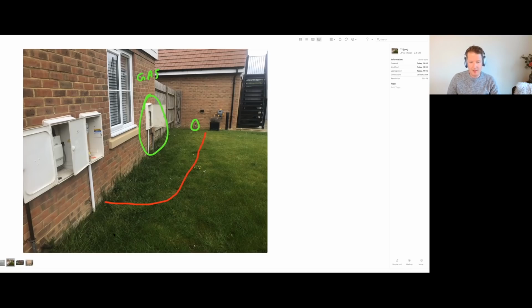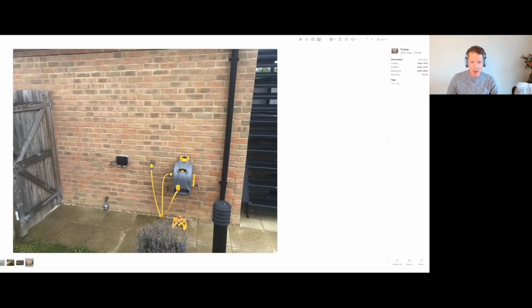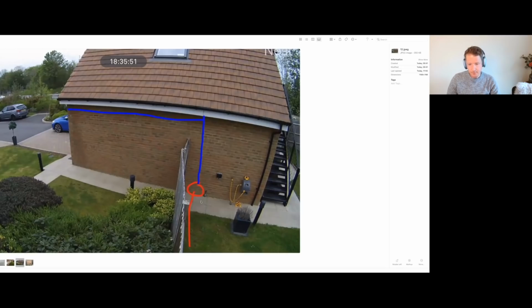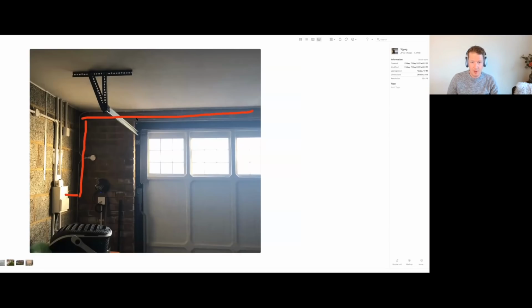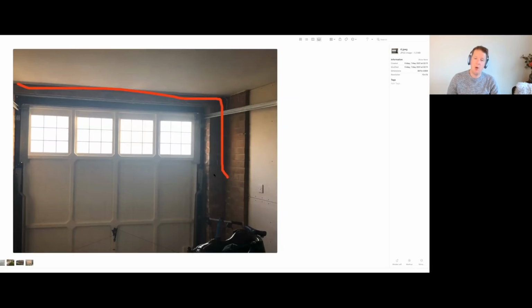So now I'm thinking, okay, we get the customer to get a trench dug, get something run underneath that pavement, and then maybe they put a 63 mil cable duct in all the way into the garage, and then we can run the cable in afterwards. That would be good. And then inside the garage, all we have to do is pull the cable in and clip the cable within the garage. It would come in here somewhere, for example, in the duct, and then we'd clip it to surface inside the garage all the way through and follow a similar route to what the customer showed us in the pictures. Surface clip the cable along here, along and down, and then we could drill through and go straight into the back of the electric vehicle charging point.